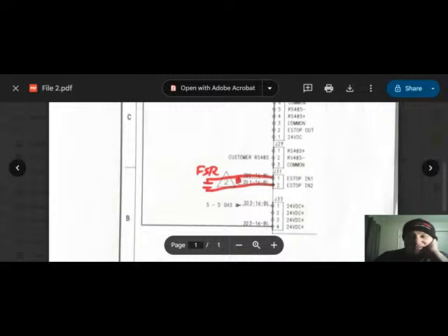Reason for that is if you went with the normally closed contacts to maintain this loop and you relied on the relay powering up to open the contacts and cause your restart fault, well, if that coil all of a sudden decides to burn out or something, you're not going to know it until you actually need this loop. Doing it this way, keeping the relay powered up and relying on normally open contacts to maintain closed, if that relay coil goes bad or something else goes wrong with that relay, you're going to know it because you're going to get an e-stop call.